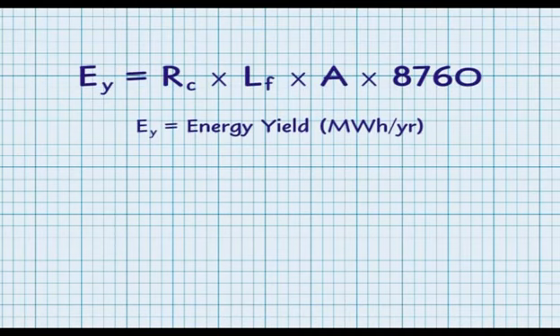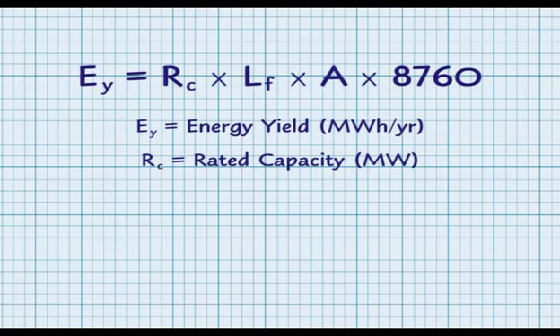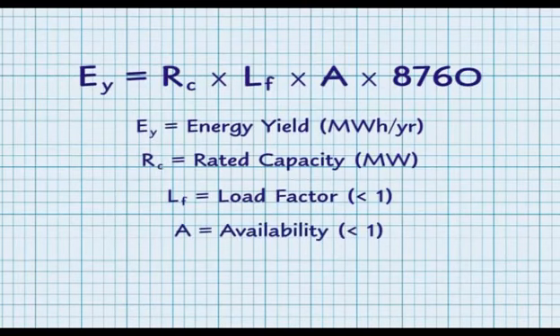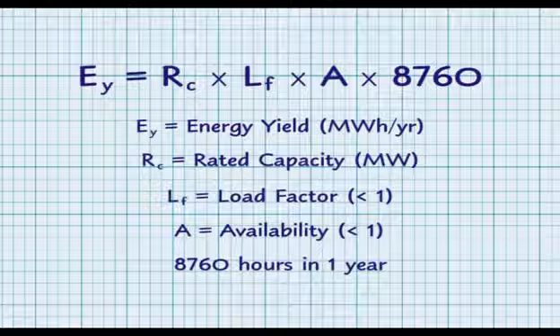Energy yield is equal to RC times LF times A, multiplied by the number of hours in a year. RC stands for rated capacity of the wind farm, typically in megawatts. LF is load factor — this accounts for the fact that the wind doesn't blow all the time, and hence we have a factor of less than one. A is for availability, which accounts for things such as reliability of the wind turbines and the time to repair them, so in a full year we won't have 100% availability due to mechanical failures.